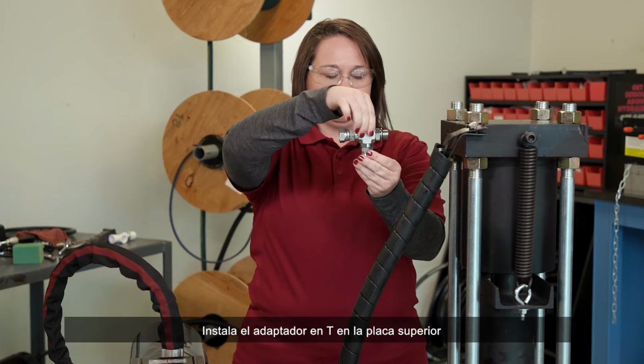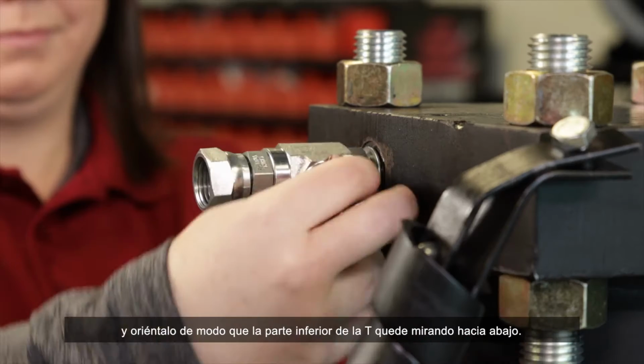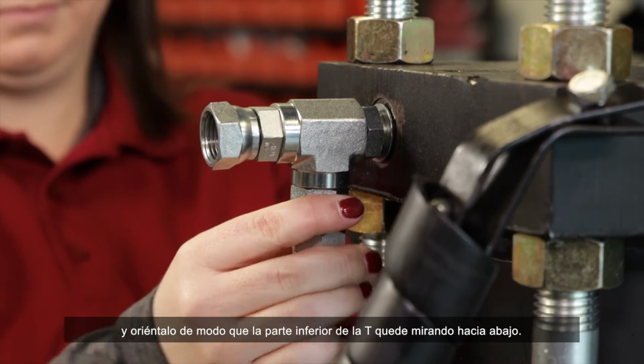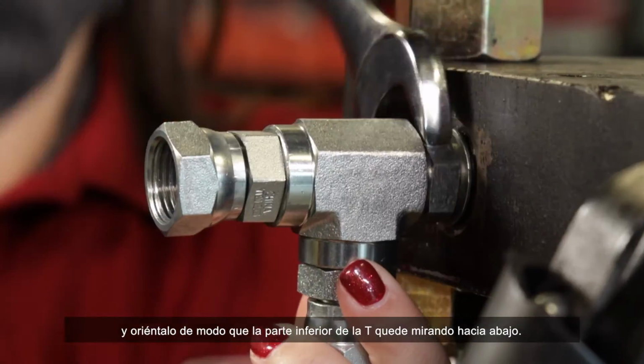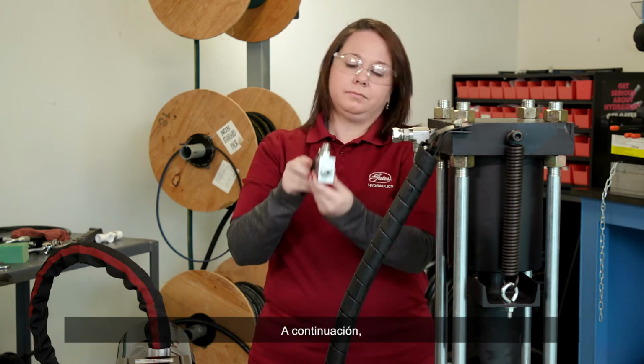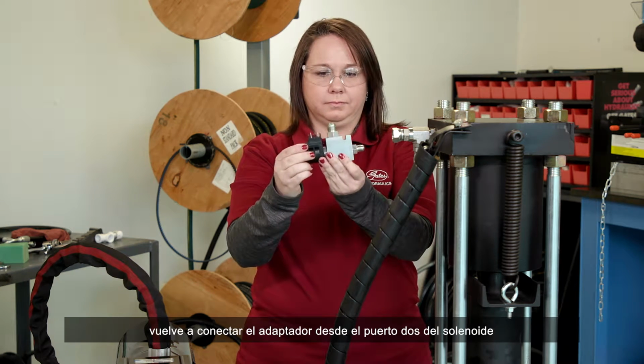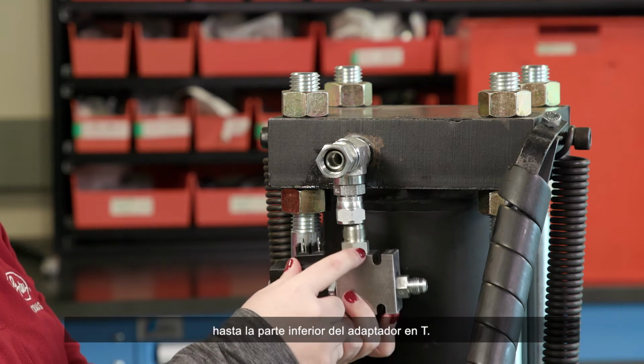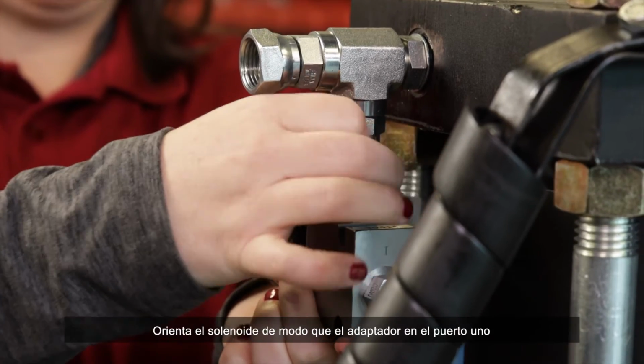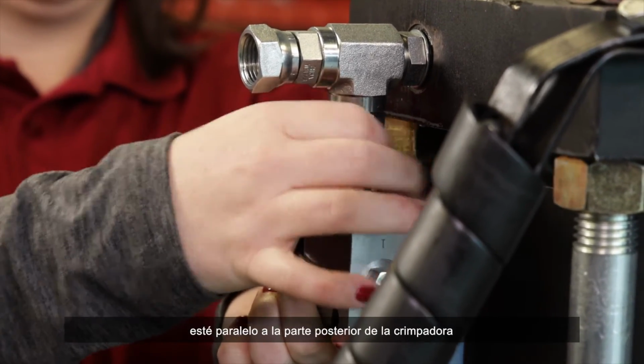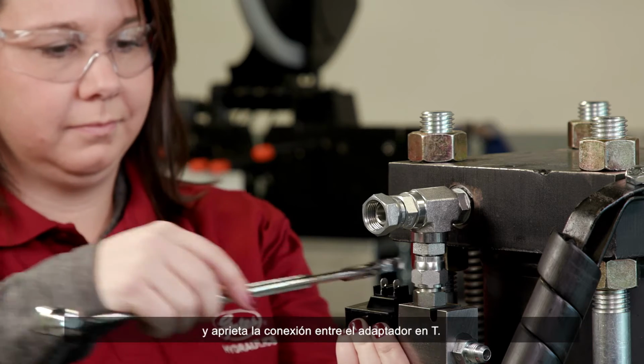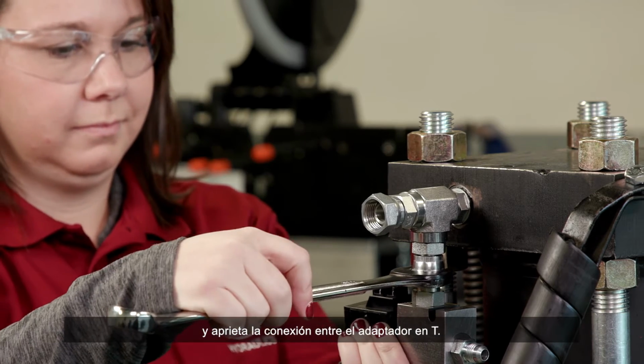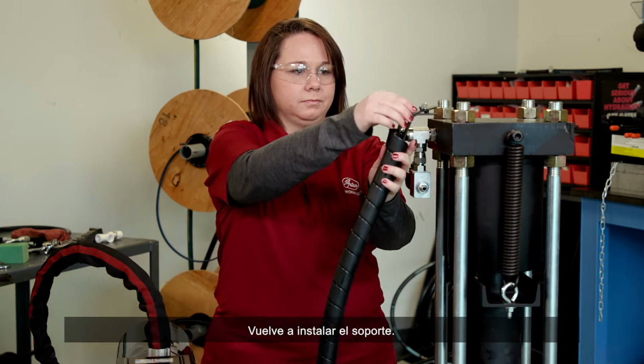Then install the T-adapter to the top plate and orient it so the bottom of the T is facing down. Tighten. Next, reconnect the adapter from port 2 on the solenoid to the bottom of the T-adapter. Orient the solenoid so the adapter in port 1 is parallel to the back of the crimper, and tighten the connection to the T-adapter. Reinstall the support bracket.